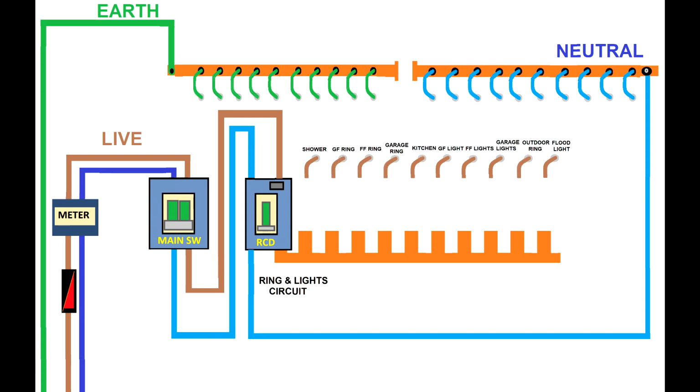So I also talk about the not really bad but inconvenient, from a maintenance standpoint, way of using only one residual current device. If you use one residual current device, then you'll see clearly in this picture that the residual current device will provide power to the entire bus bar, which provides power to all these circuit breakers. So if you have an overloaded circuit, it's okay. Each individual circuit will break.